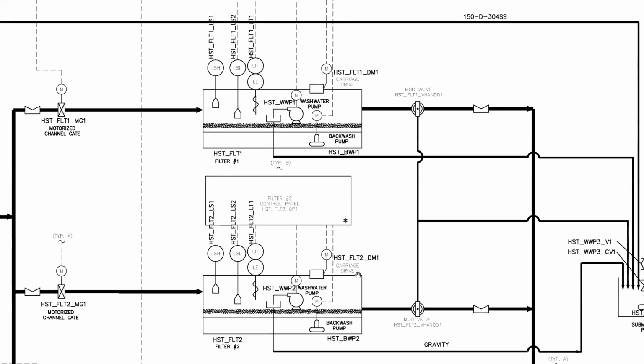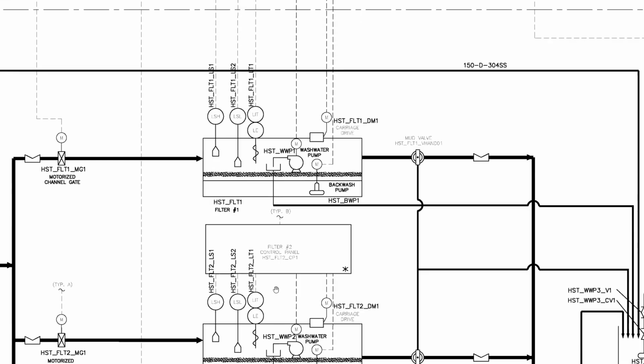And down here we have a filter bridge 2. So we have FLT2, LT1. So hearkening back to the tagging that we were talking about, I think a couple weeks ago, this is an example of a client who has a standard that you've got a filter 1 and specific tags for that, and a filter 2 and specific tags for that. So the level transmitter is always going to, if you had a third bridge, you'd have a filter 3 and then a level transmitter for that.